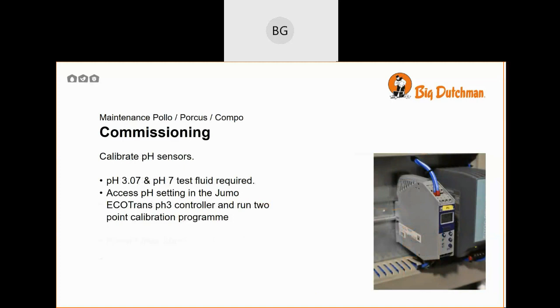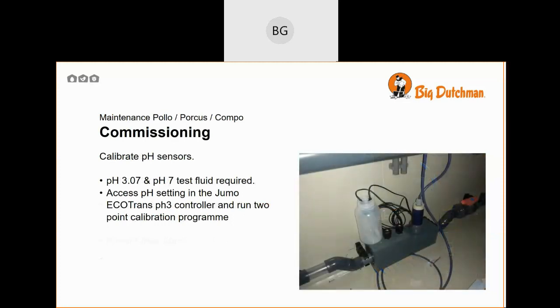Calibrate the pH sensors. You require pH fluid at 3.07 pH and 7 pH. Access the pH settings in the Jumo ECOTrans pH3 controller and run the 2-point calibration process. This will involve placing the pH electrodes in the 2 fluids provided.